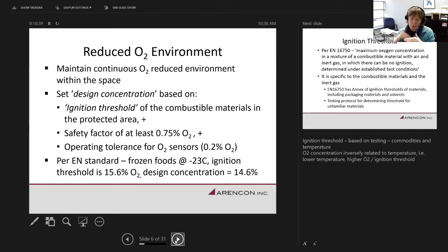So we want to hold the oxygen concentration at a level below the ignition threshold. So we add a safety factor, which per the standard is at least 0.75% of oxygen, plus an operating tolerance for the oxygen sensors, which have an accuracy of plus or minus 0.2%. So the design concentration and the operating threshold is typically about 1% below the ignition threshold.